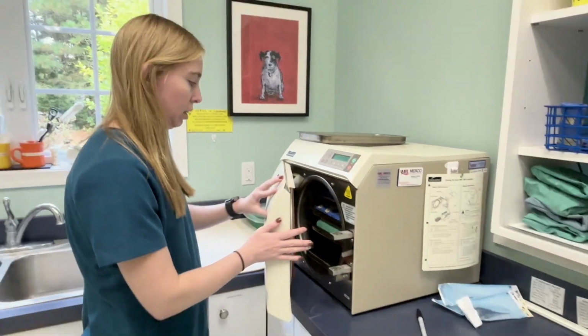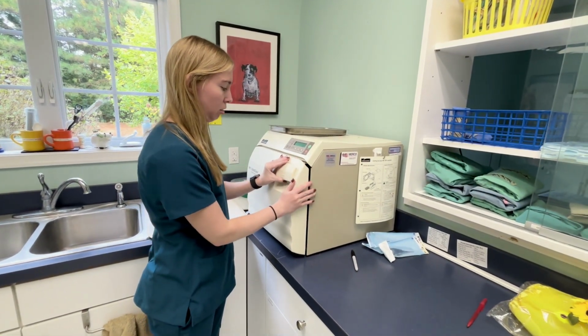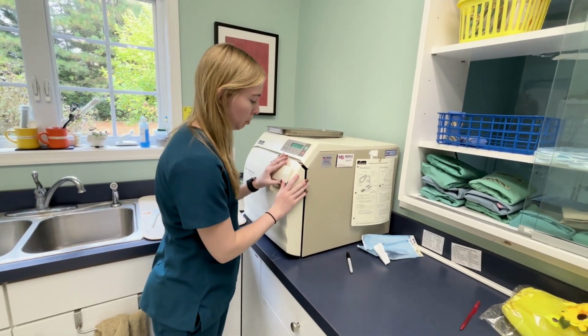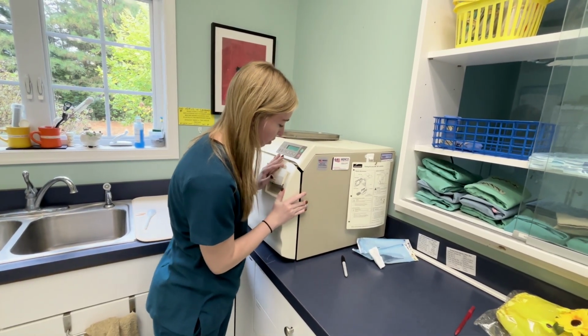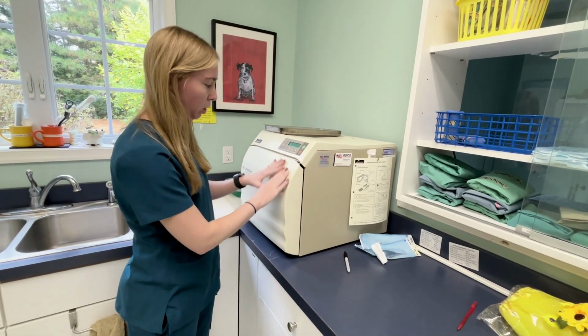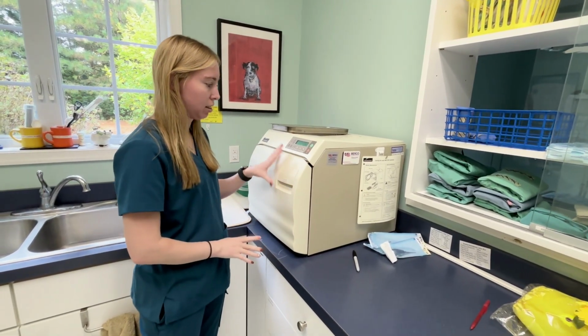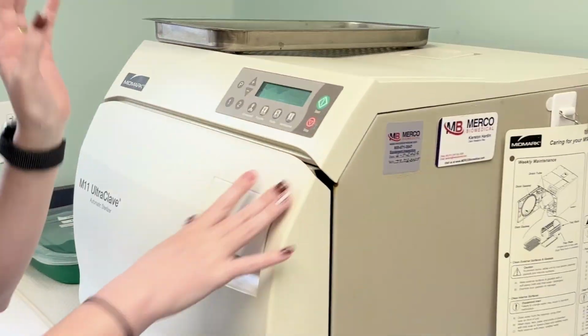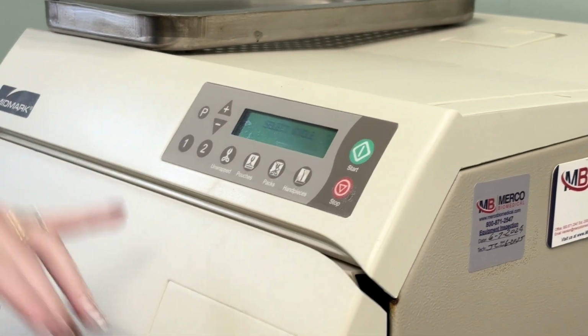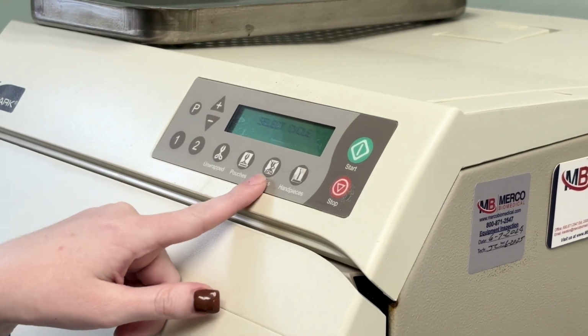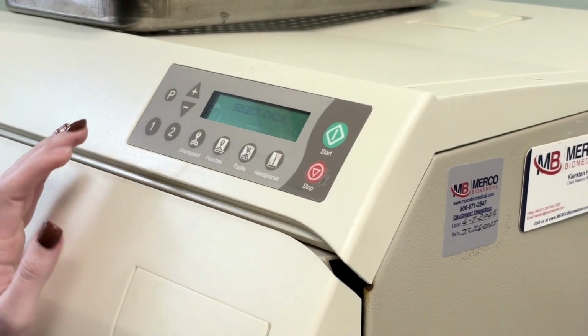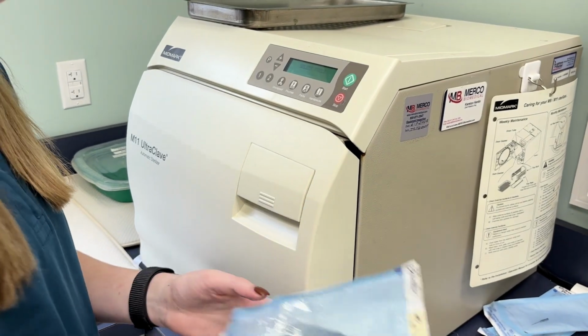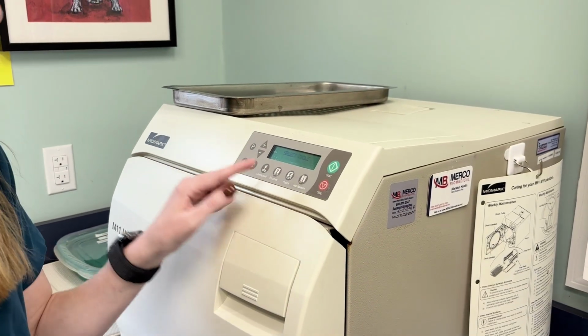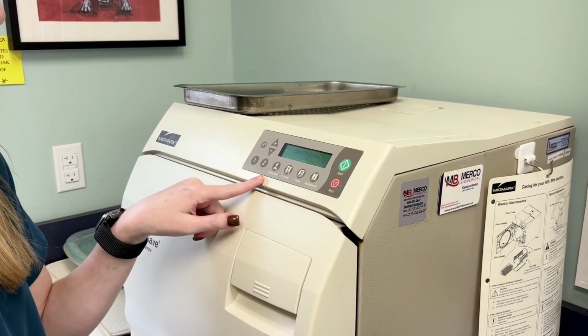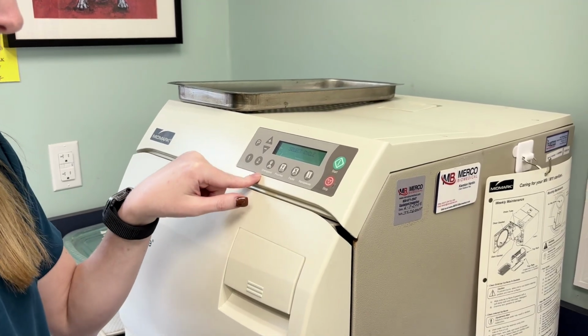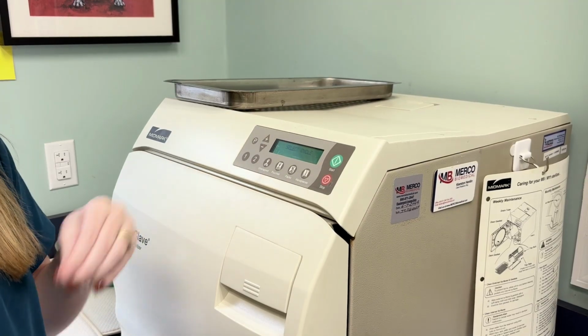What you're gonna do is, it has a little handle, you just go up on it, and sometimes this one is a little older, so you just push and then it'll lock into place. So now the door is shut, and we can pick our sterilization. All of my instruments were packed into packs, so I will be using the pack setting. We also use pouches such as these ones, which are going to be on a different setting. The packs are run at 250 degrees Fahrenheit with a pressure of 15 psi, and they're sterilized for 30 minutes and then they dry for 30 minutes.